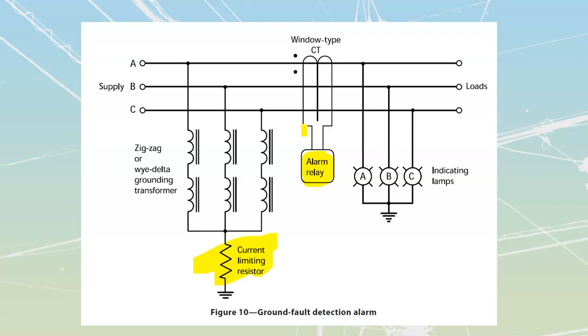Now we know that the net sum of all the currents inside a delta system is going to be 0 - we've seen that before, where we add those phasors together and they come back to form a value of 0. Which means that if the net current is 0, the net flux is going to be 0, so I'm not going to establish any voltage over top of this alarm relay. It's going to be shut off, and my lights as well are going to be shut off at this point.